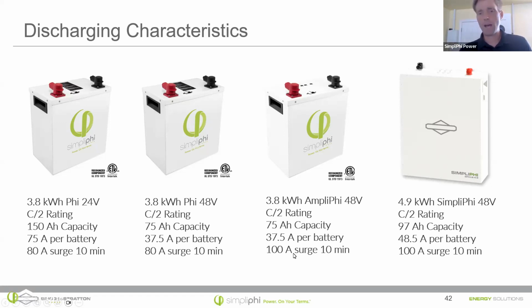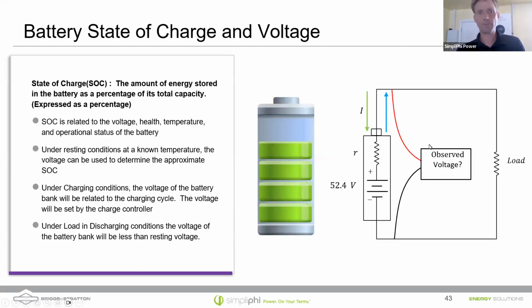That's the maximum this battery will output, but typically this battery will be sitting at 53 volts fully charged. So you can get over 100 amps at 53 volts, which would be over 5 kilowatts of power out of a single battery. You can do that for up to 10 minutes for a real surge if you need a lot of power for a short amount of time. The SimpliPhi battery can also surge up to 100 amps for 10 minutes. Again, limitations based on the breaker and the BMS there, but that's a huge amount of power out of these batteries for a limited amount of time.